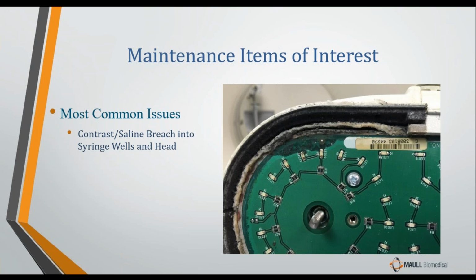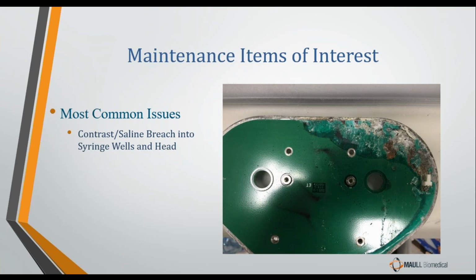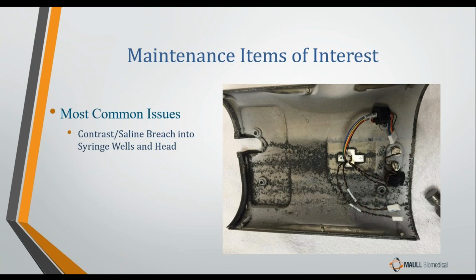These are just a few pictures of a Stellant that, to be honest, I have no idea how they let this much contrast get into the head. This is the worst case scenario here. A couple other pictures here. This is the LED board, and you can see the corrosion that the contrast did to this particular board. This is the back plate, the back cover of the Stellant that we took off, or that the guys took off, and you see the damage that was done here. I've never seen anything this bad, but this is the damage that contrast fluid getting into the injector head can do.